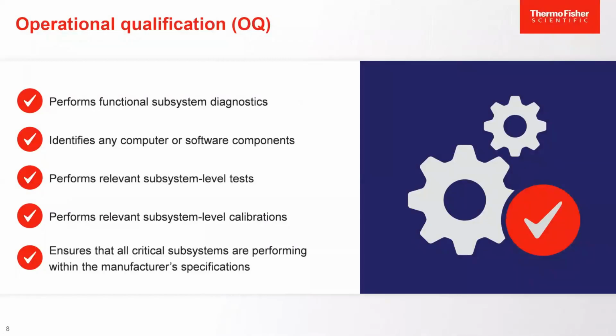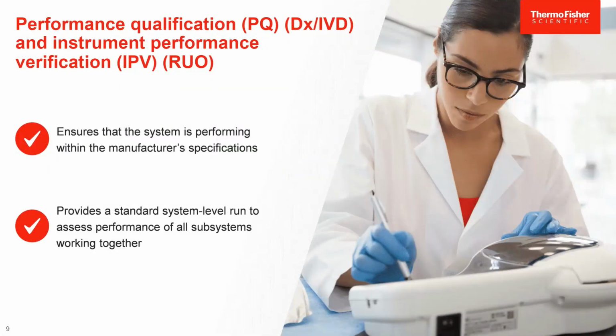The next step would be your operational qualification. During this, we'll perform functional subsystem diagnostics. This also helps to identify any computer or software components, performs relevant subsystem level tests, performs relevant subsystem level calibrations, and ensures that all critical subsystems are performing within the manufacturer's specifications. Next, we would lead to the performance qualification and instrument performance verification. During this, we're going to ensure that the system is performing within manufacturer specification. This provides a standard system level run to assess performance of all subsystems working together.